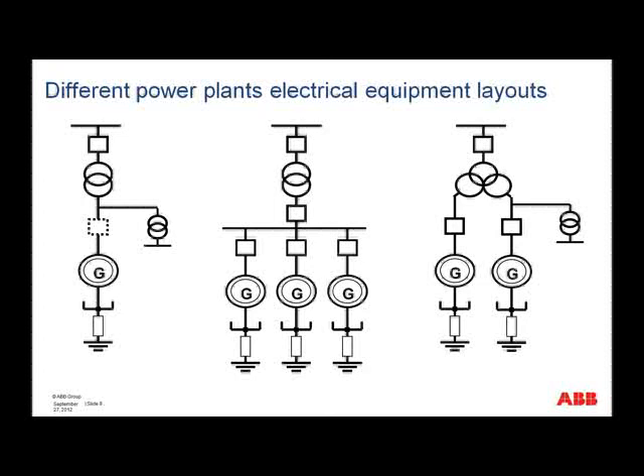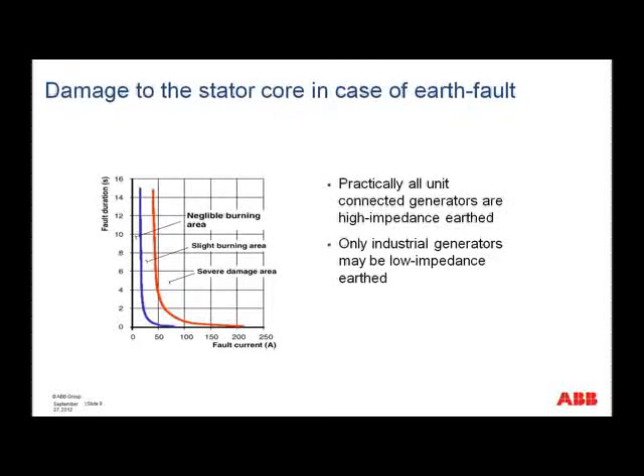Now, there can be, of course, a number of different equipment layouts in a power plant, and this would depend, of course, on the size of the generator. And if we look at the left there, you can see a single generator with or without the generator breaker connected to a unit transformer for connection to the network. In the middle, we have where more than one generator is connected to the same step-up transformer, and possibly these would then be for smaller generator sets. And then on the right, we have a picture which is typical for small hydro units.